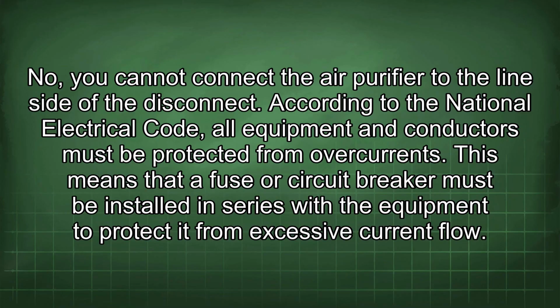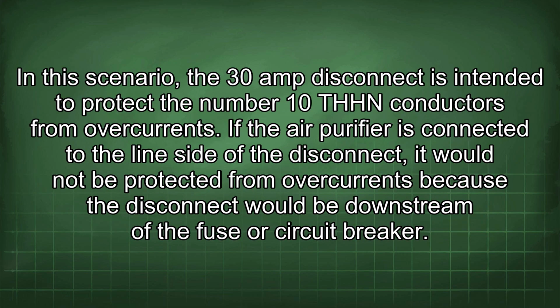No, you cannot connect the air purifier to the line side of the disconnect. According to the National Electrical Code, all equipment and conductors must be protected from overcurrents. This means that a fuse or circuit breaker must be installed in series with the equipment to protect it from excessive current flow. In this scenario, the 30-amp disconnect is intended to protect the number 10 THHN conductors from overcurrents.